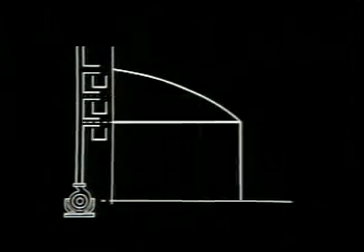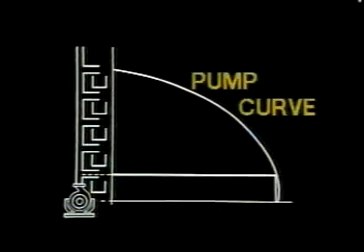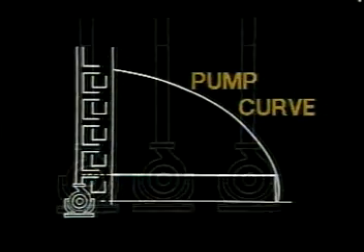Comparing the two types by filling a balloon with water: the positive displacement pump will keep pushing water into the balloon until it bursts. The centrifugal pump, however, will only inflate the balloon to the size which corresponds to its maximum total head — at that point, it cannot supply any more liquid into the system. The vertical distance it can reach in the pipe is referred to as the head, and at maximum head the pump has reached its minimum capacity output. As the pipe is directed to empty into tanks at progressively lower levels, the head is effectively reduced and the pump increases its flow rate. By graphically depicting these results, a characteristic pump performance curve is drawn.